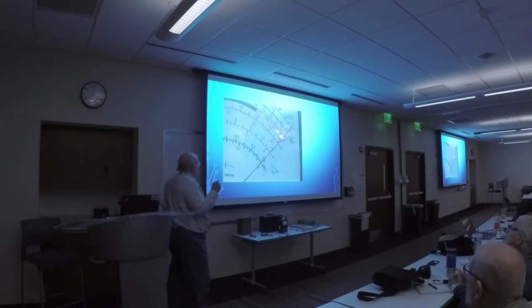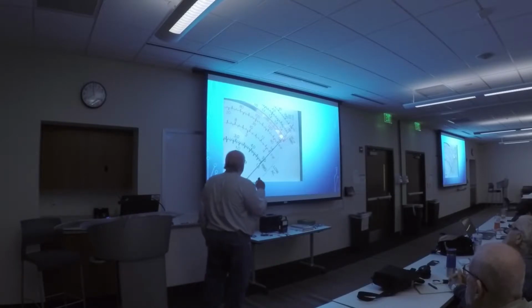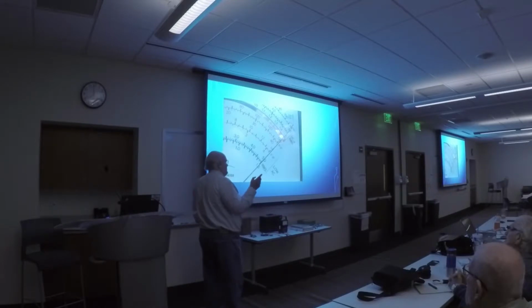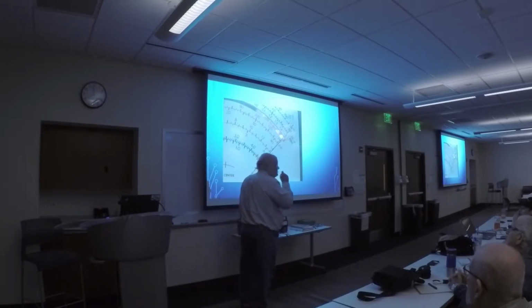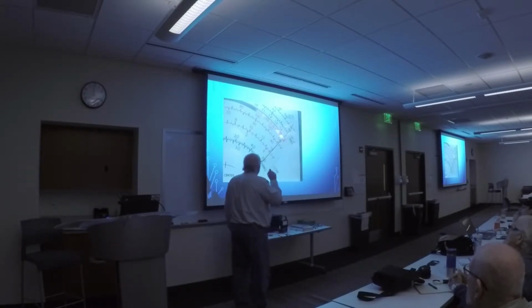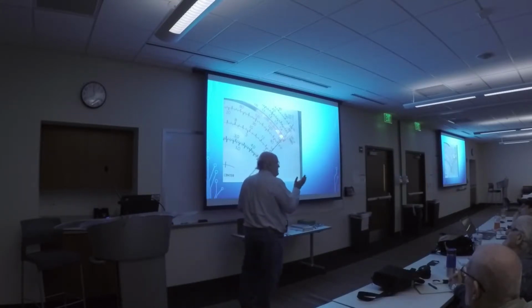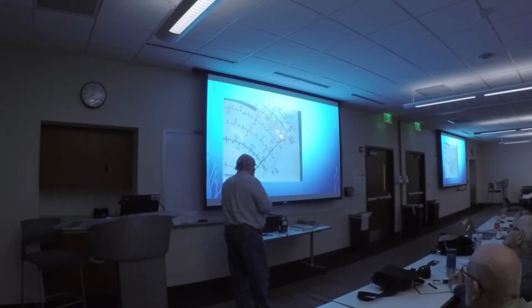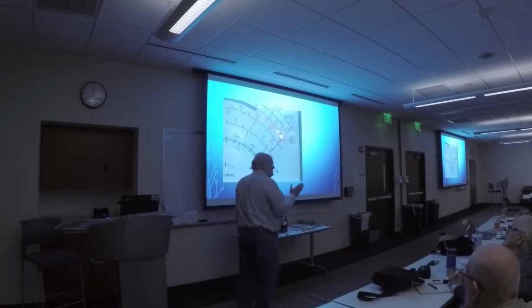So this is a little closer look at it. This is in the ohms mode, because you see when it's open like that, it works reversed on ohms. So when you turn it all the way to ohms, the meter swings all the way over. And that's when you use your 0 ohms. So you see it right here. Now this is good because it shows you what you use the mirror for. If you look at this closely, you'll see the meter, the actual pointer. Then behind it you see an image. That's the back of the pointer. So the idea is you take the actual mechanical pointer and line it up with the image in the mirror. And when you do that, you are guaranteed a correct reading, because as you look at it on an angle, it'll move around. Parallax. Yeah, parallax. As a matter of fact, that's what they call this mirror. They call it anti-parallax.